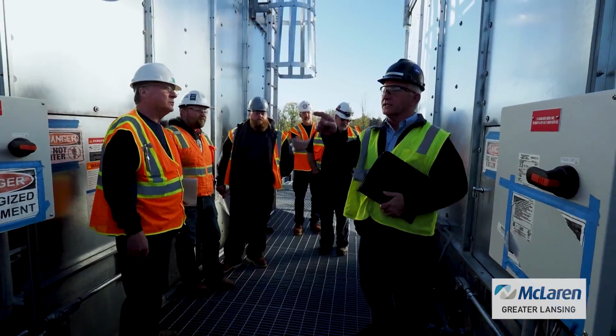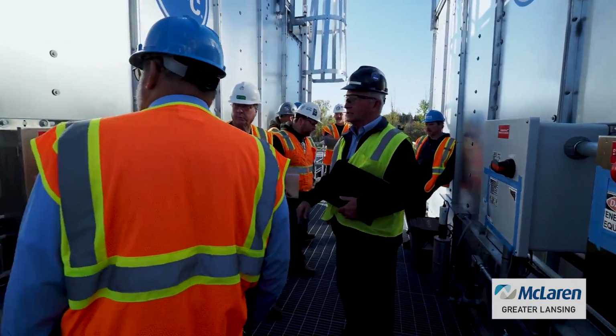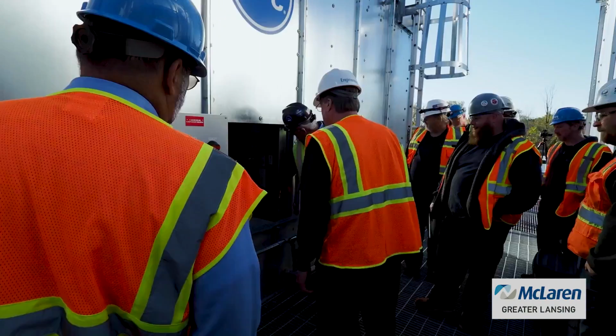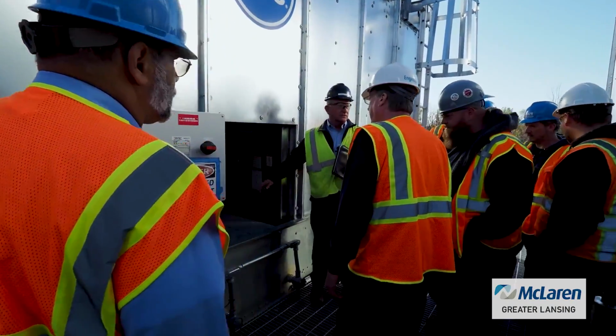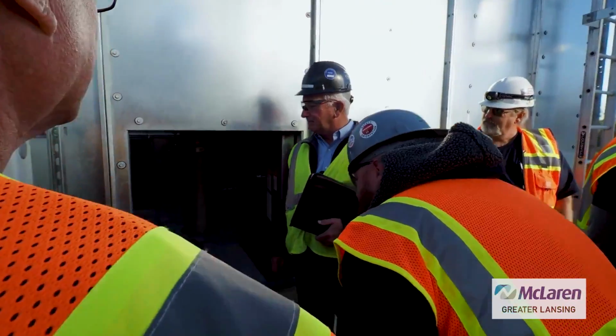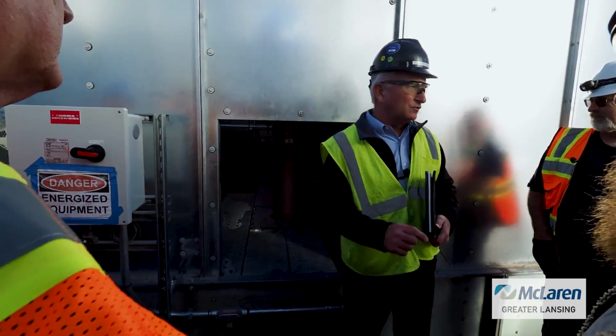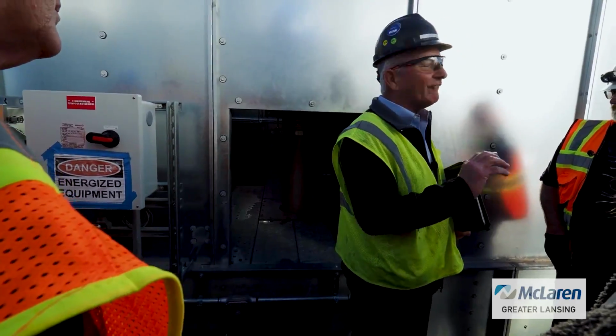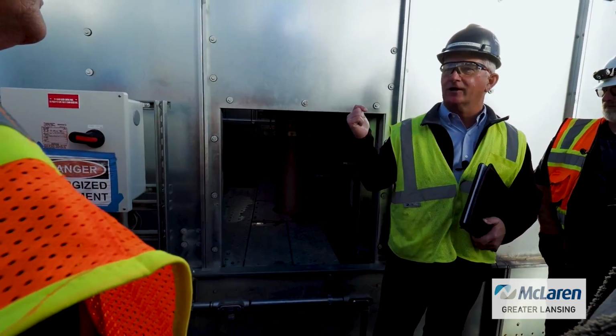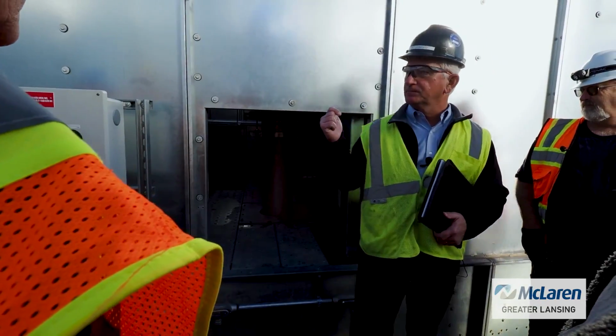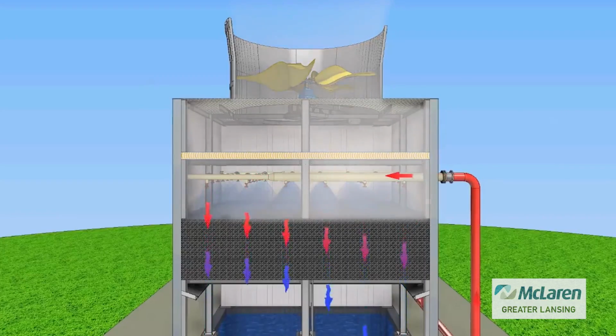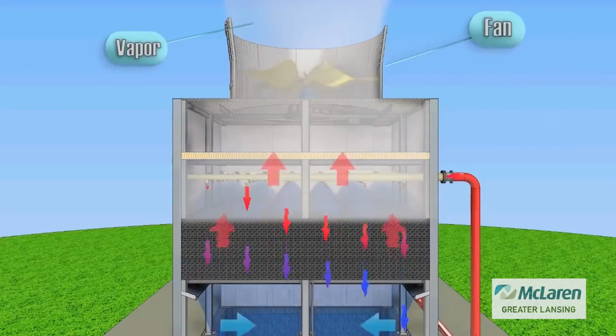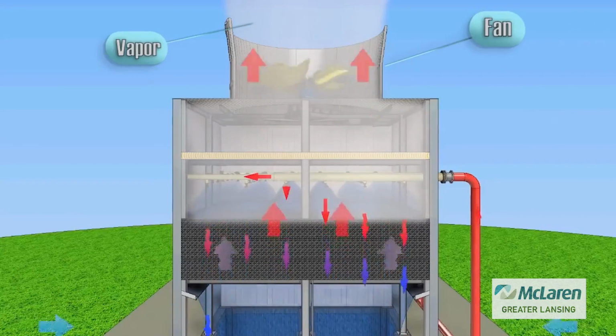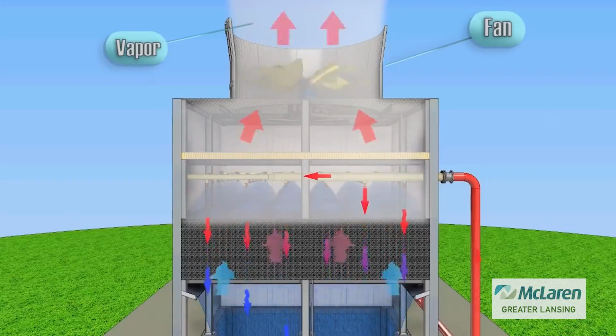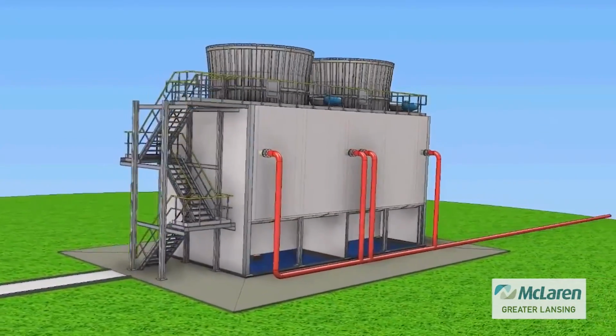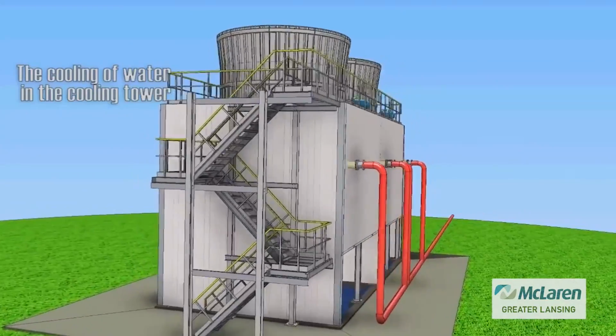All right, so let's throw the disconnect switch on the fan motor to this tower. You do have internal walkways, so you don't need to wear boots. Generally speaking, it probably is a good idea to come out here with somebody else. You never know. If you go in there, you don't have a hard hat on, you hit your head and boom, knock yourself silly, fall in the water. The potential exists. That would not be a positive outcome. So perhaps have somebody else out here, or be really careful when you're going into the tower. If we were to go in right off the gate, here's a headbanger. Right? So want to avoid that.